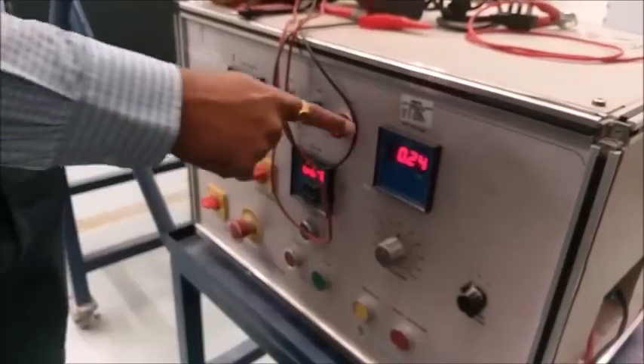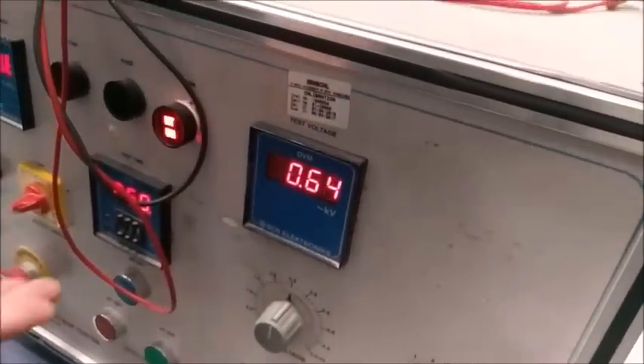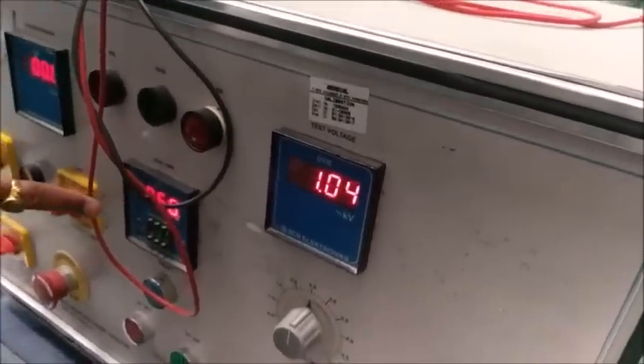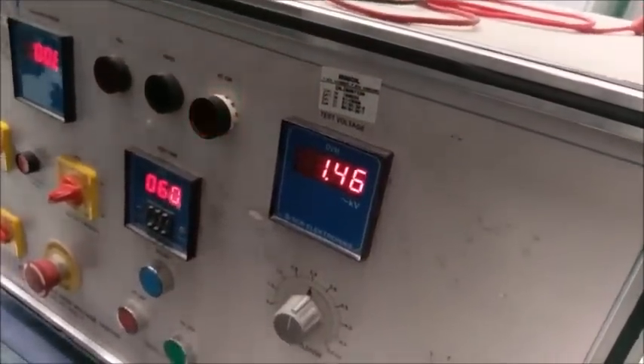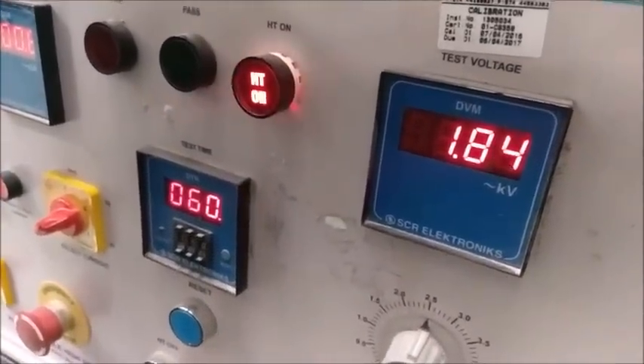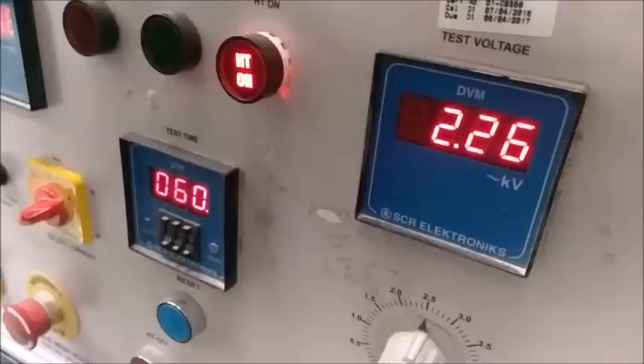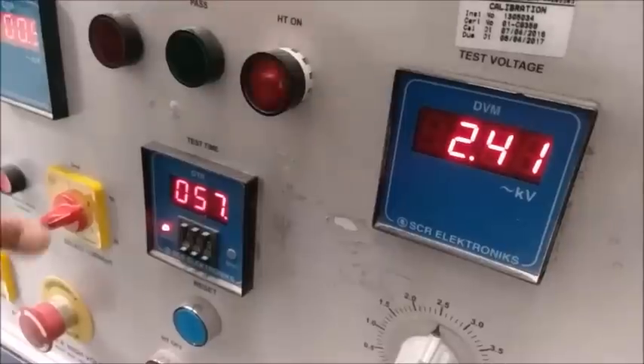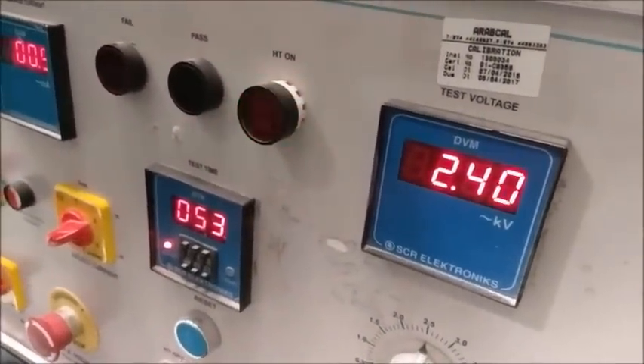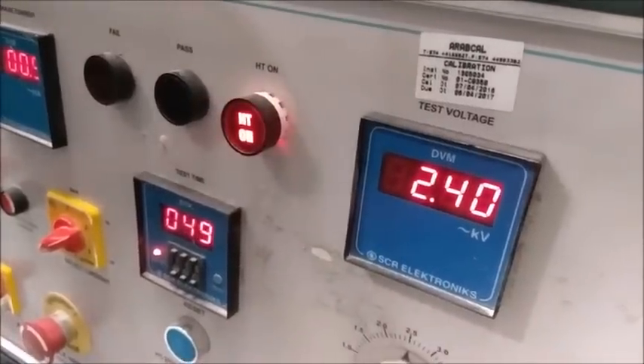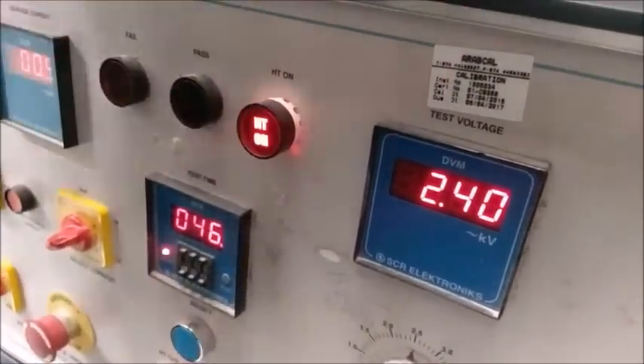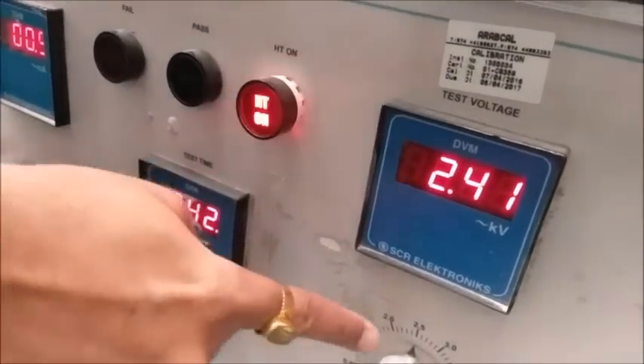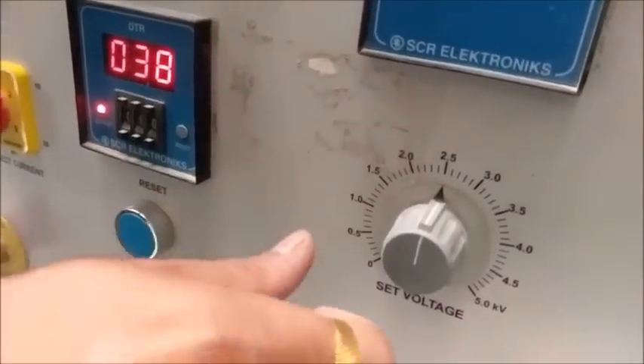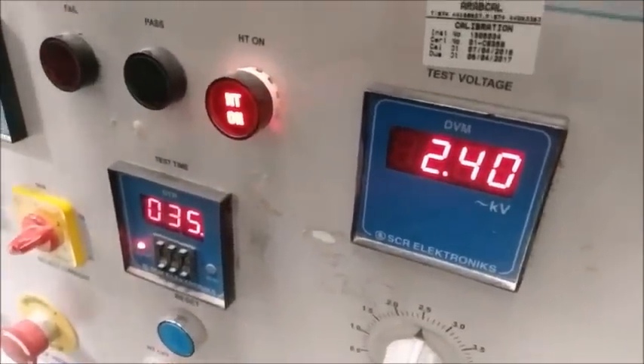Let's see the test. Now the voltage is building. Do not touch, no one touch. The timer is at 60 and until it reaches 2.5, it will hold, and then count down 60 seconds. Now it is operating. Why is it not exactly 2.5? A 0.1 error is always there. We can increase it, but this is a common step. See, now it is at 2.5. We can increase with the knob like that, so it is not manual adjustment.